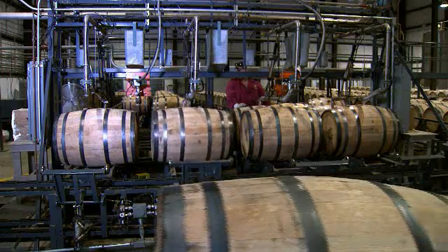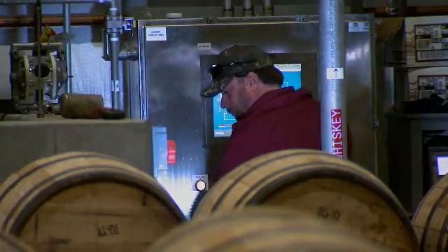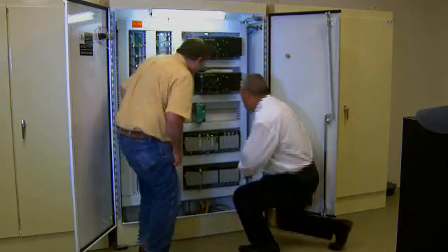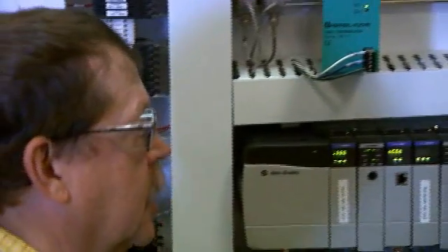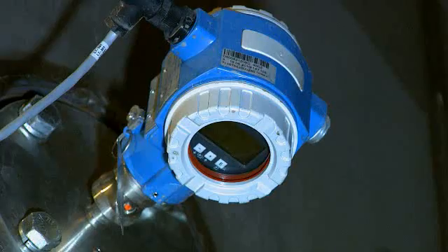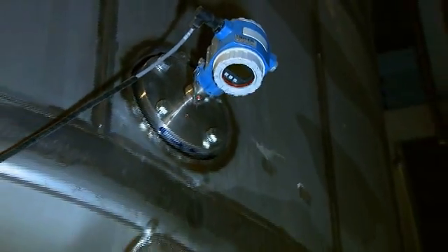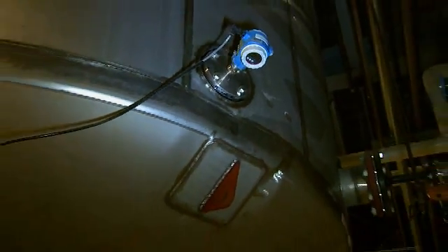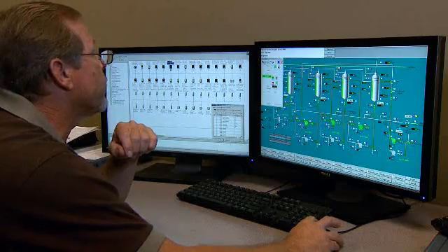We were given a boilerplate package that was to be placed over the top of our facility. We worked together and discussed each step of the process from beginning to end. We went with the Rockwell ControlLogix Platform and it's always served us well. We also utilized the LBSM — the Logix Batch Sequencing Modules — as a small S88 batching type tool. Basically all the instruments we purchased are HART-based instruments, so that it's easy to dive down into them and see what's going on internally.